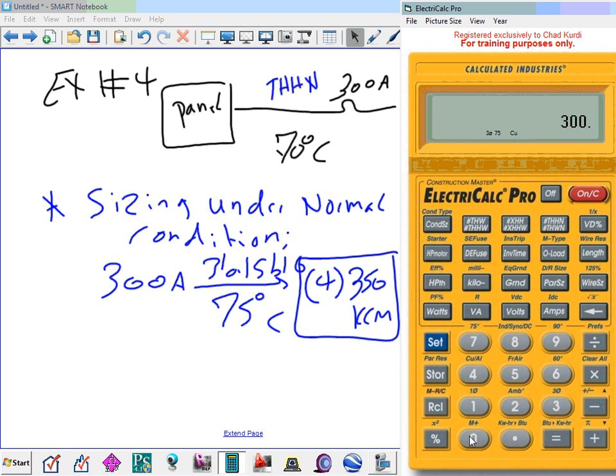You put your 300 amps and you hit your wire size and up it goes with 350, right? Is that what we got? 350. Now this is actually, I have not derated yet. So the minimum that I can use, guys, is 350. No matter what the rating tells me, my minimum is 350. Now, do I need a higher conductor size or should I stay with 350? That's what the next calculation is going to decide.